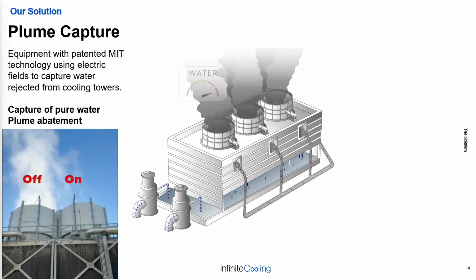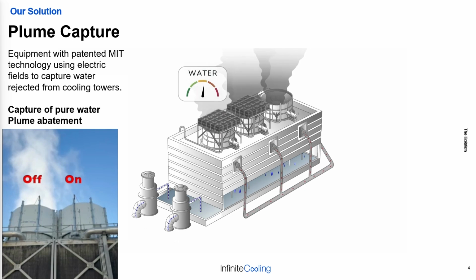What we developed at MIT and now commercialized is a technology to capture the water coming out of cooling towers for recycling. We use an electric field approach, applying a high voltage field that generates a cold plasma at the exhaust, charging the water droplets in the stream. We then use an electric field to attract those droplets to a collection surface, capture them, and send the water back for reuse.